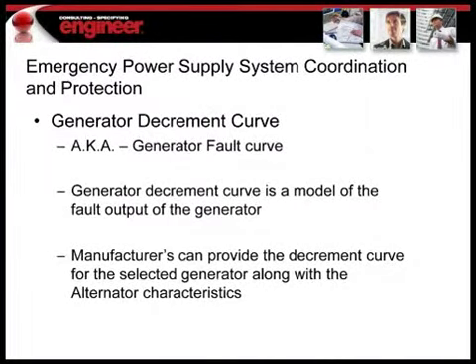The other curve is the decrement curve. The decrement curve is the generator fault curve. It's basically a model of what would happen if you had a fault, and over time what that generator performed as. The manufacturers obviously can provide that as well, but that decrement curve is tied to the same parameters, the XD double prime and all the other different parameters that I went over earlier in the presentation.